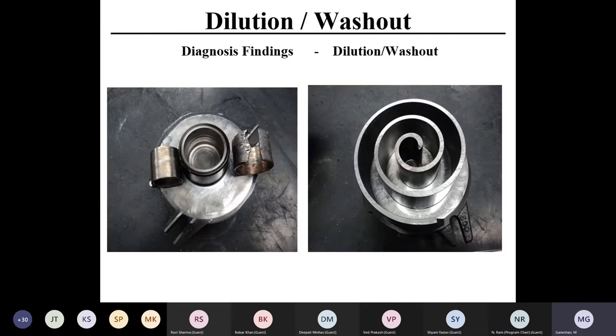So you can see what happens after dilution. Everybody knows liquid refrigerant is a beautiful cleaning agent. Wherever it goes, it can clean. So when liquid goes along with the oil, half is liquid, half is oil. When it goes to the bearing surface, what will happen? Whatever oil is lying there, it also washes away and carries it out. You can see everything shining, it has already cleaned the entire oil, and metal to metal contact is happening. So this is where simple liquid coming back into the compressor can damage the entire compressor.